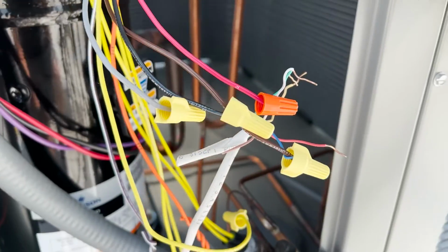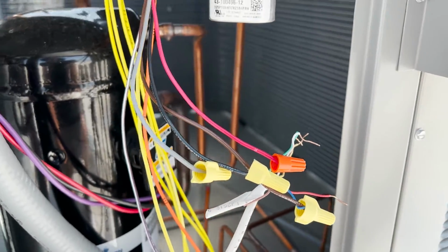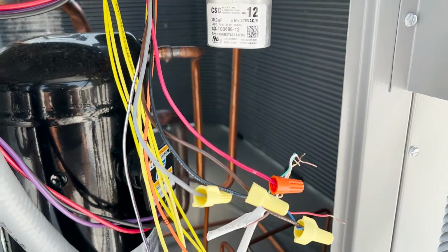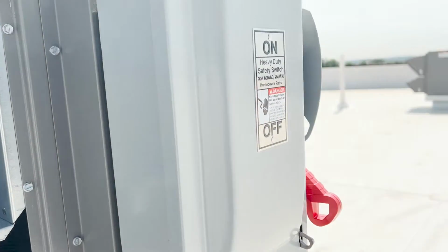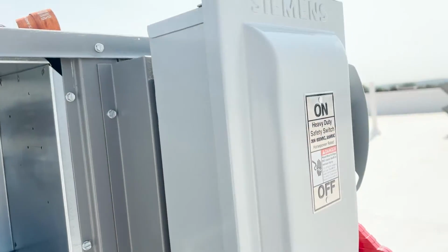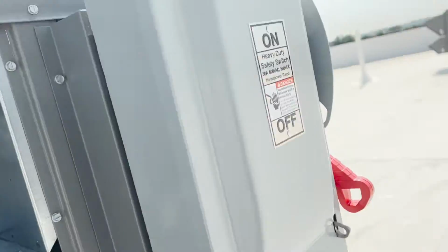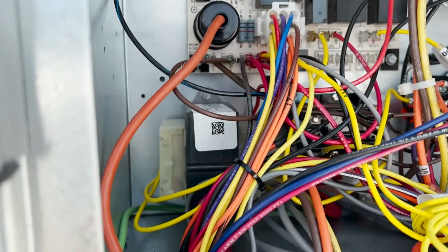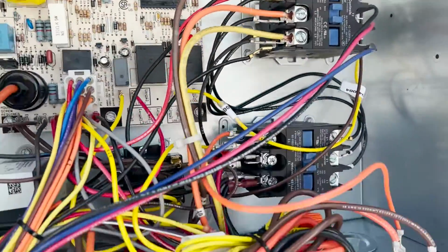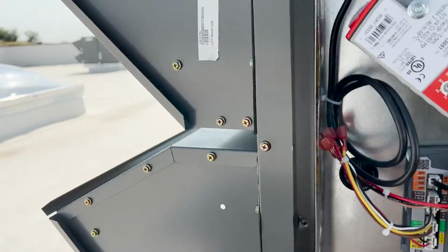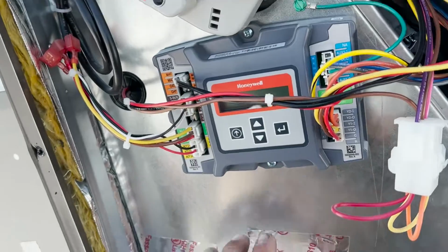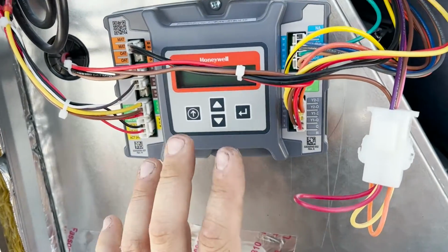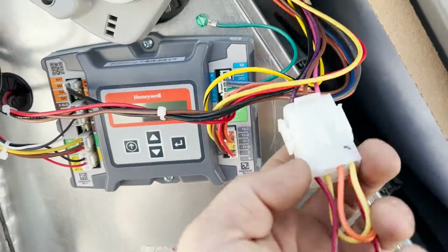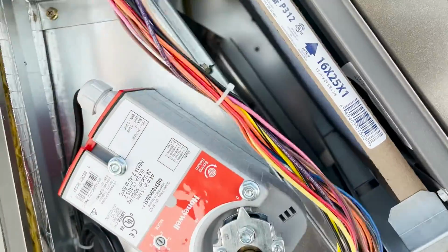I like to disconnect the thermostat, especially on this building where I don't know what's connected and what's not. And then we're gonna go in for voltage, make sure that that's right. But before we flip the switch, we're gonna check that our transformer's tapped right and look for any loose wires in this cabinet. All right, step 2 on commissioning, the economizer, right? So we're getting ready to power this on. First, we want to make sure that our jumper's in place, we're connected.